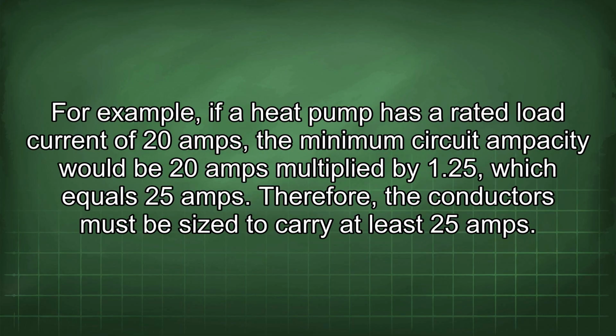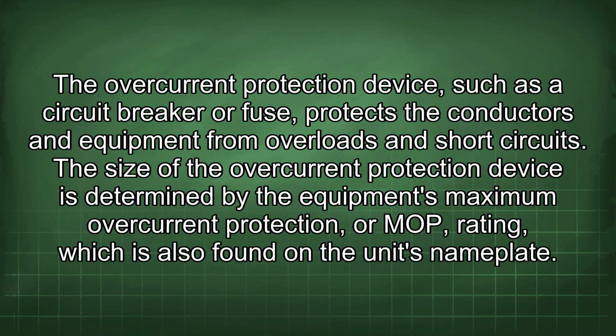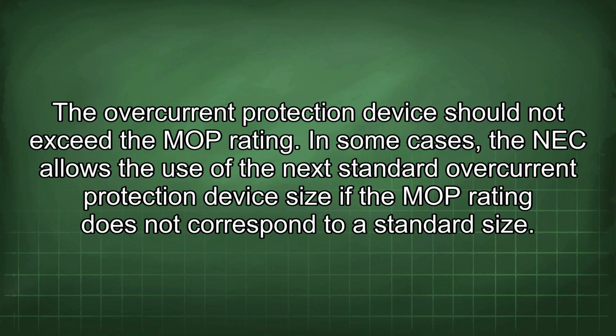For example, if a heat pump has a rated load current of 20 amps, the minimum circuit ampacity would be 20 amps multiplied by 1.25, which equals 25 amps. Therefore, the conductors must be sized to carry at least 25 amps. The overcurrent protection device, such as a circuit breaker or fuse, protects the conductors and equipment from overloads and short circuits. The size of the overcurrent protection device is determined by the equipment's maximum overcurrent protection, or MOP, rating, which is also found on the unit's nameplate. The overcurrent protection device should not exceed the MOP rating.